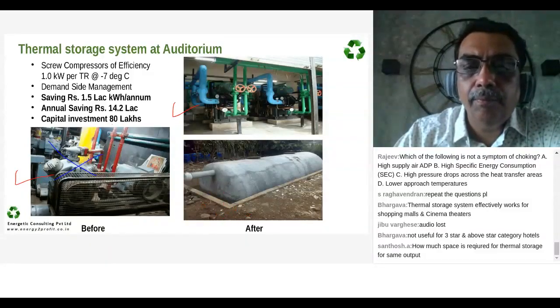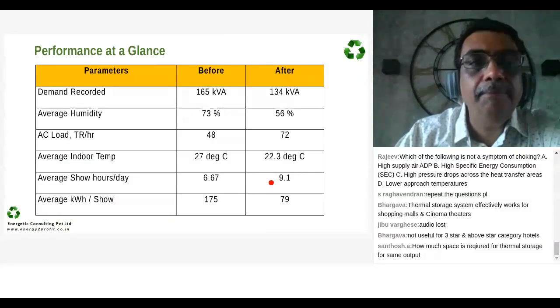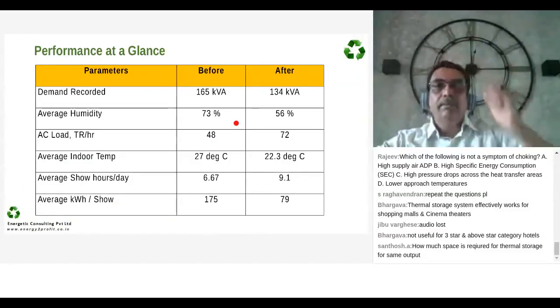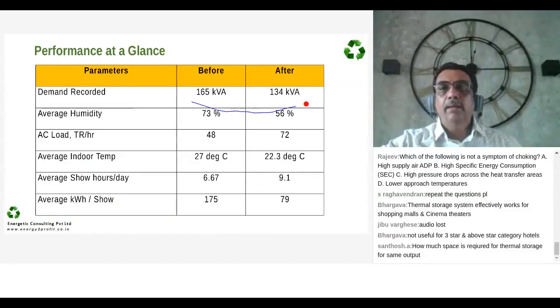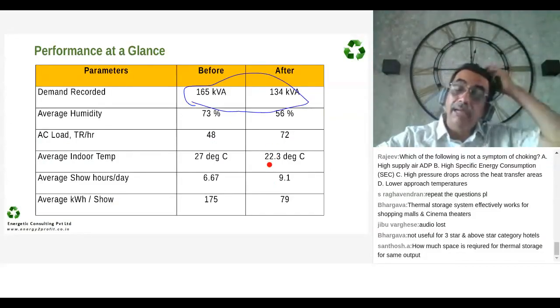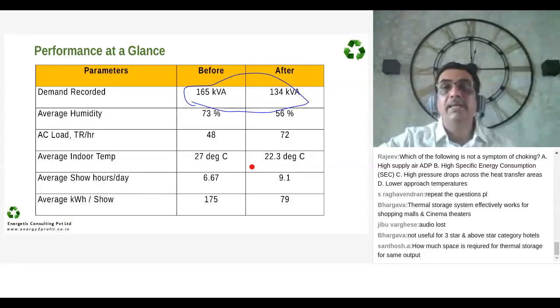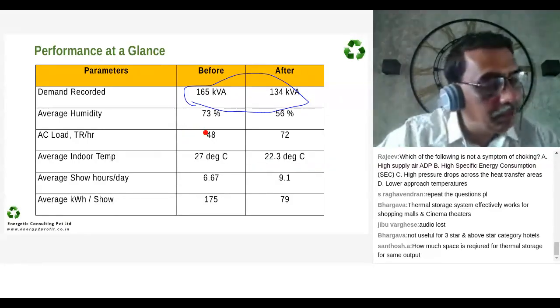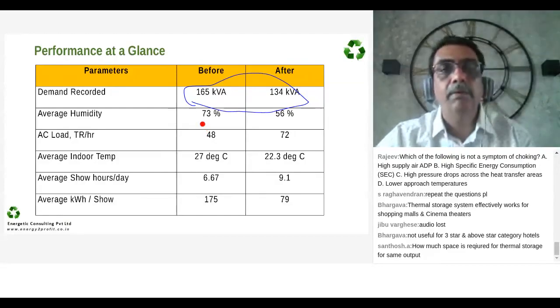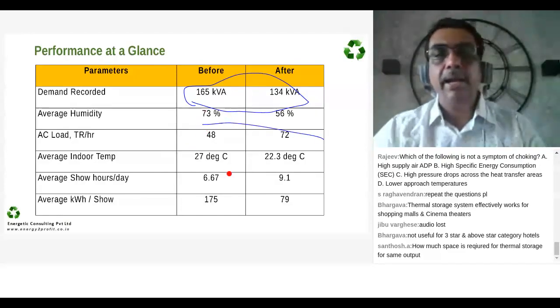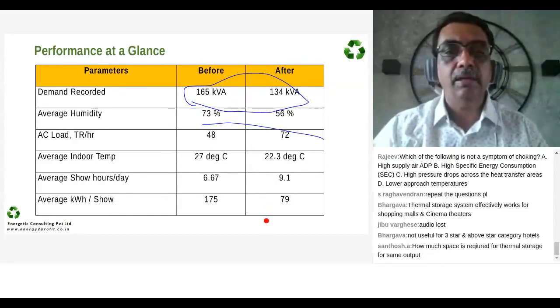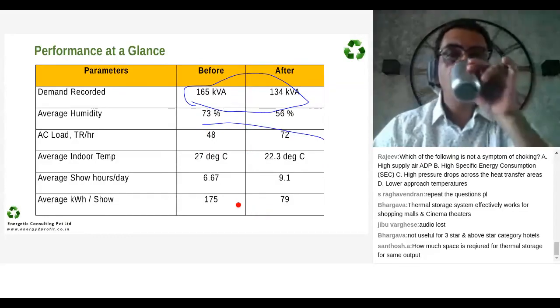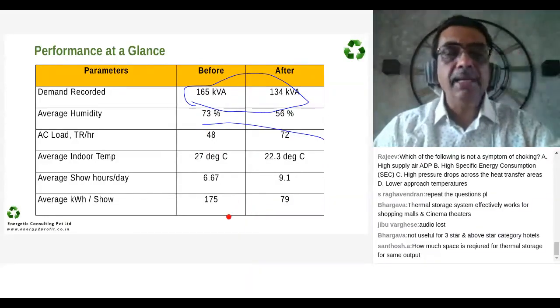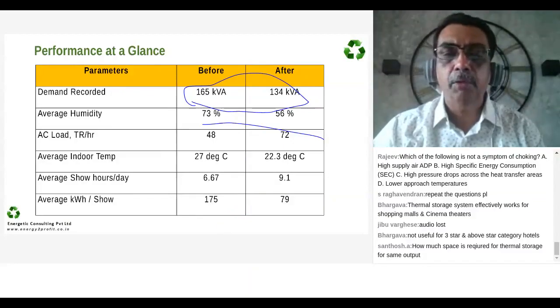Now, what did we get out of it? A 30 kVA demand reduction. Again, percentage-wise, if you see, it's about 20% reduction. But the facility had a major advantage because of the humidity reduction and the temperature control, which was proper. Being an auditorium, this was very important for them to maintain.